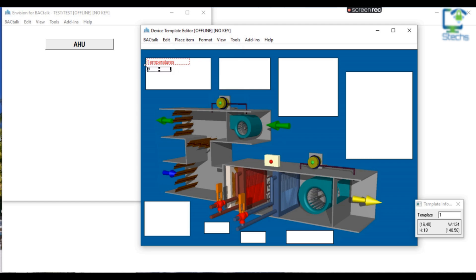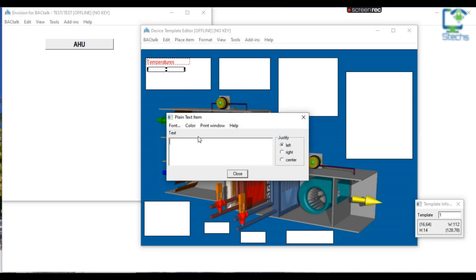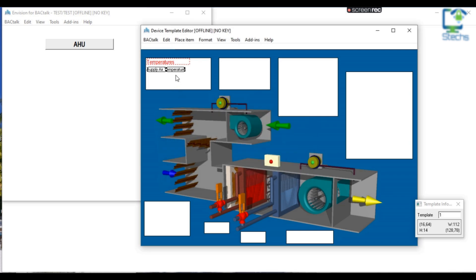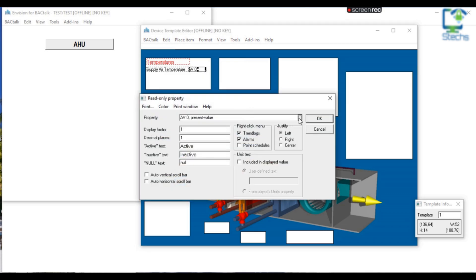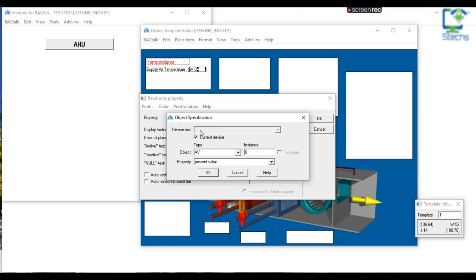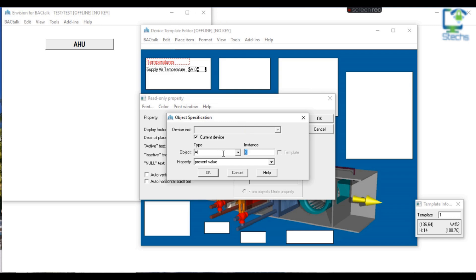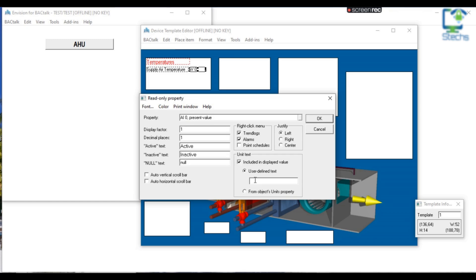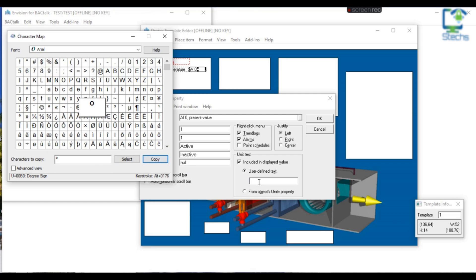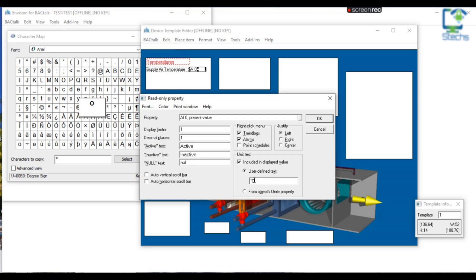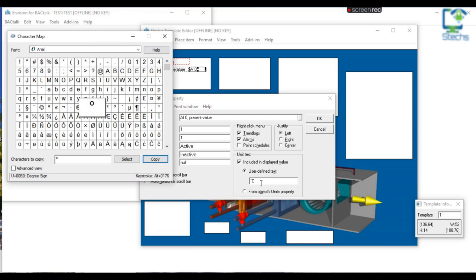From the plain text editor I am adjusting the font style and size, and from the Color menu I am changing the color of the text to red. I added a new plain text template, double-clicked on it, and added the text as "Supply Air Temperature". To add temperature parameters, I am choosing Read-Only Property from Place Item. Double-click on the read-only property and select object type and instance. Since temperature is an analog input, I am choosing AI in the Type column and instance 0 in the Instance column. To display the unit of the supply air temperature, I selected Included in Display Value from the Unit Text column and chose user-defined text. To add a degree symbol, I chose the character from the Windows Character Map, then copied and pasted it into the unit column and added capital C.